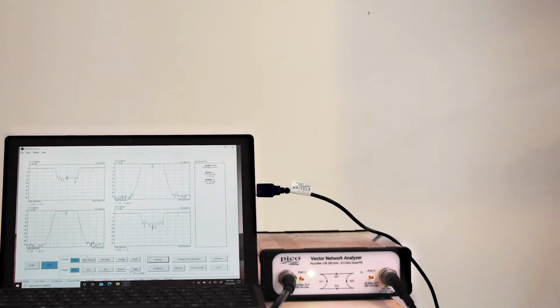The VNA field calibration, in contrast, is performed by the user prior to each new set of measurements. It is performed entirely at a software level, without opening the enclosure, and it takes only a few minutes. It is often performed several times a day, whenever accurate measurements are required.